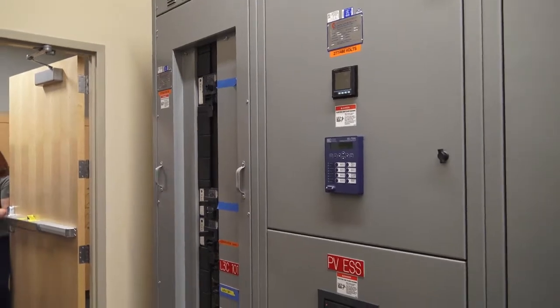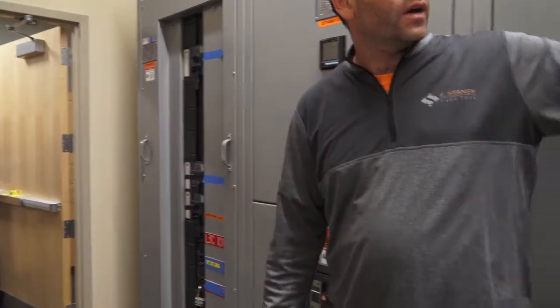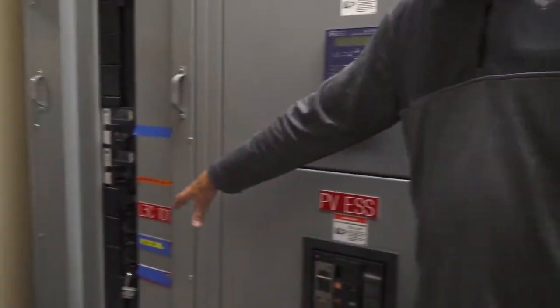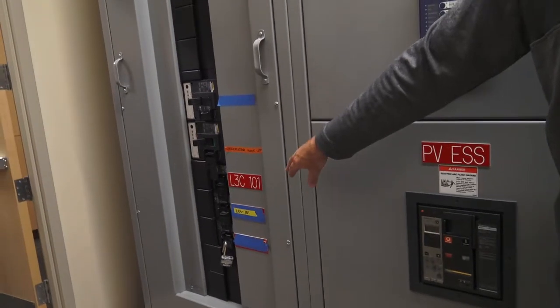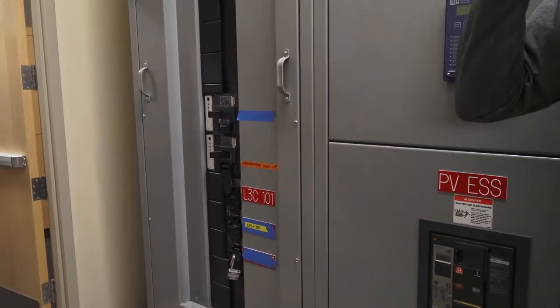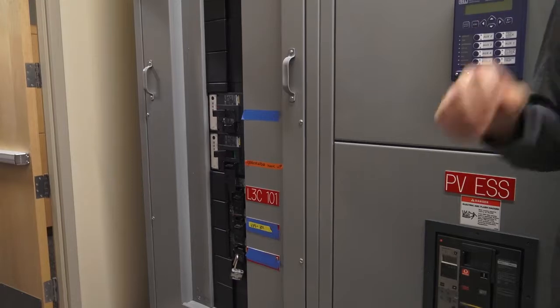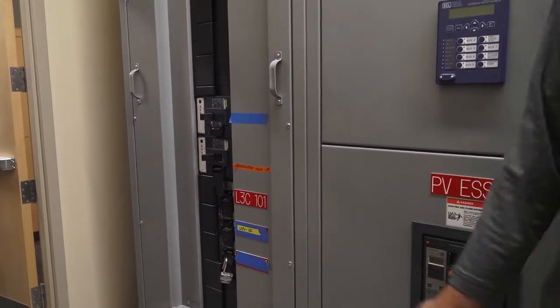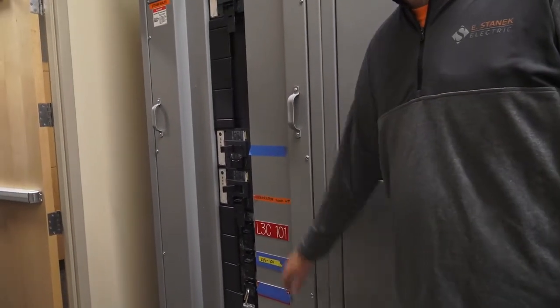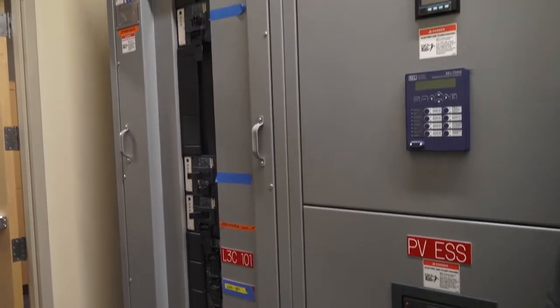Right now, while we do not have the battery here, we have a temporary generator, so that's why stuff's padlocked off and taped over. We combined two of the panels together to get the generator, to get the elevator on the generator and keep all the lights on the generator. Right now the critical is not being fed at all from the temporary generator.